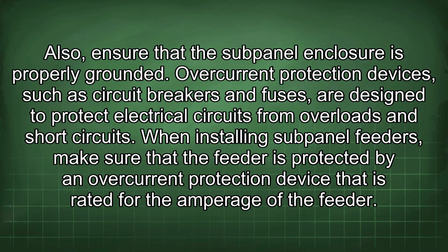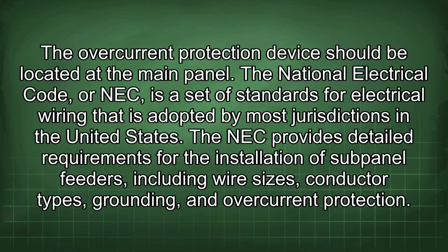Overcurrent protection devices, such as circuit breakers and fuses, are designed to protect electrical circuits from overloads and short circuits. When installing subpanel feeders, make sure that the feeder is protected by an overcurrent protection device that is rated for the amperage of the feeder. The overcurrent protection device should be located at the main panel.